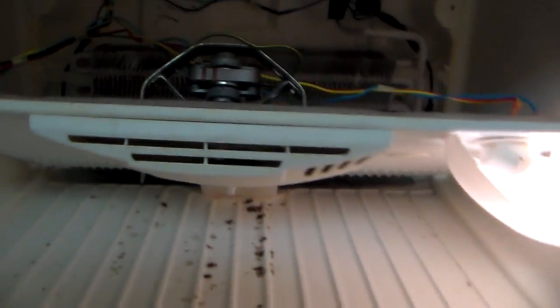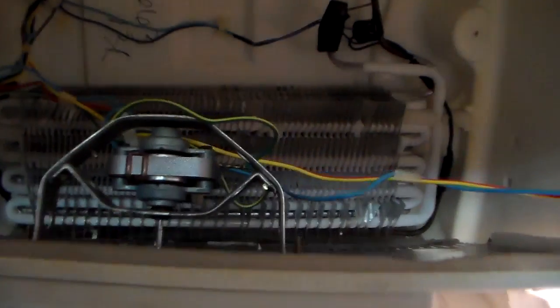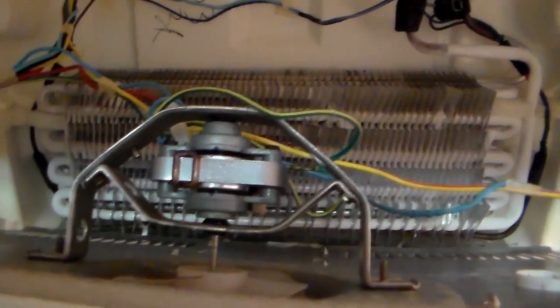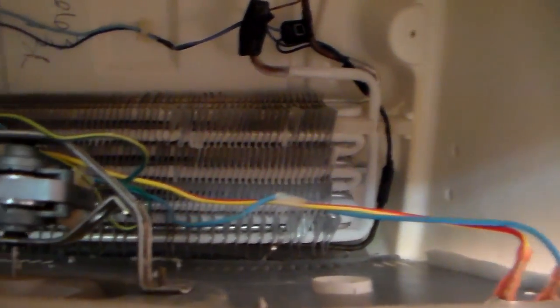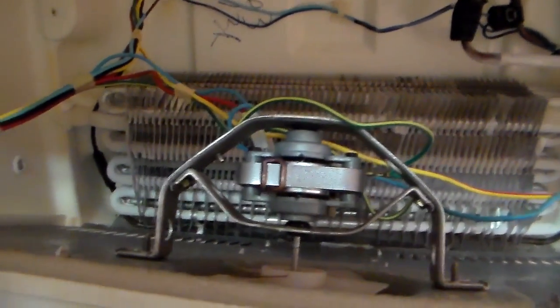Now if you advance that timer into the defrost right there, if you advance that into defrost everything shuts off and that heater never comes on, then you're going to have to troubleshoot a little bit farther than just the timer. We'll get into that here in a second, but I'm going to stop this while this runs for about five minutes, then we're going to check it.